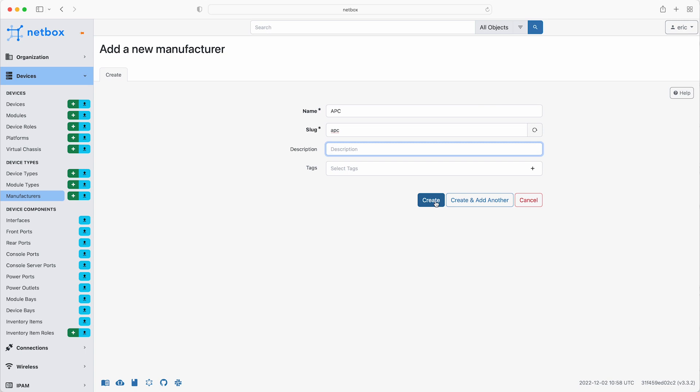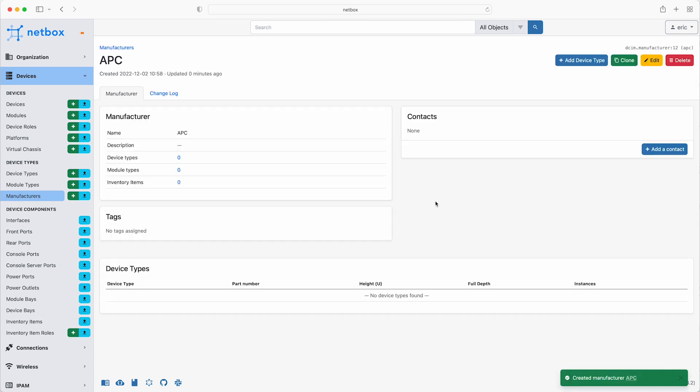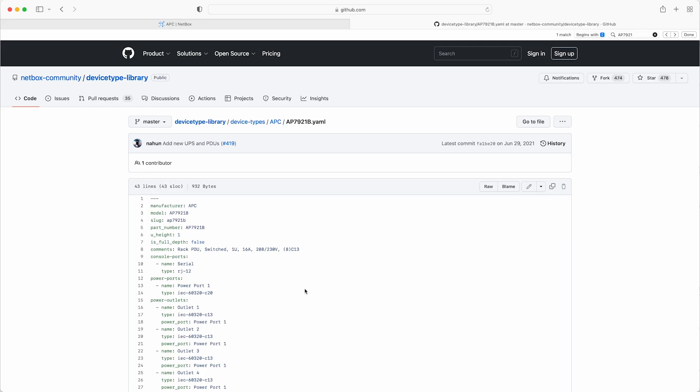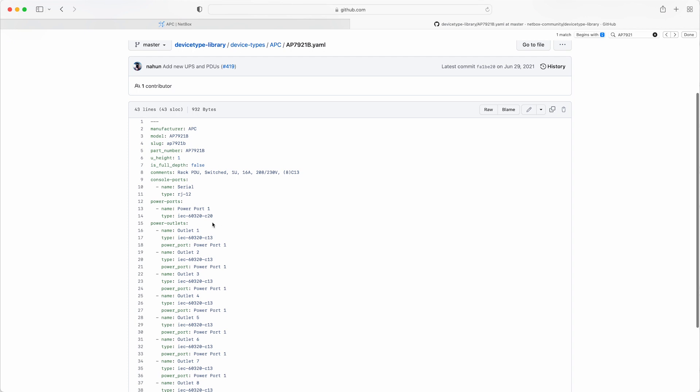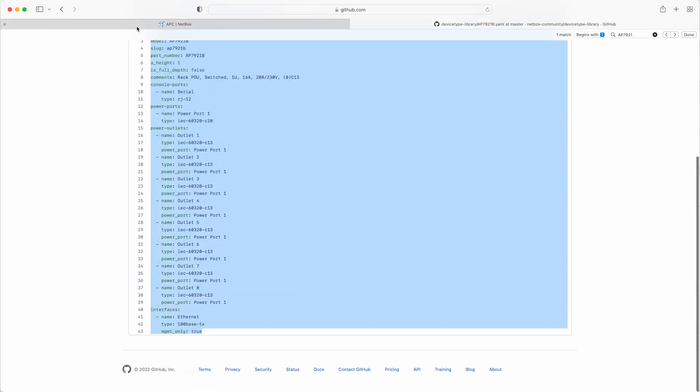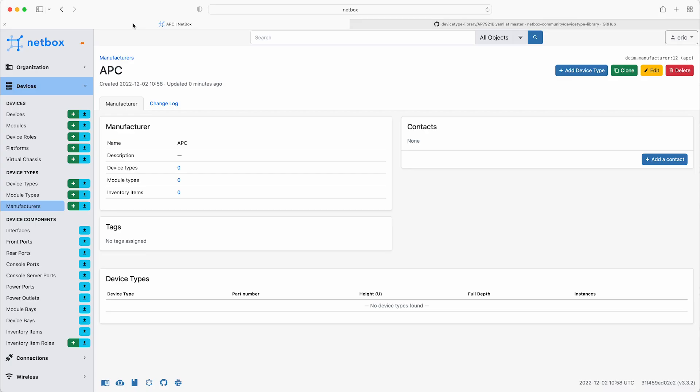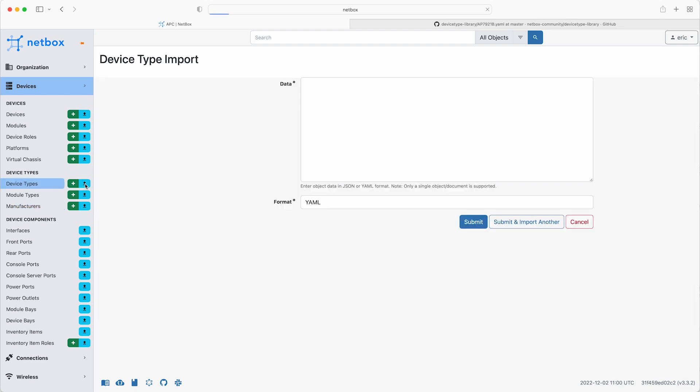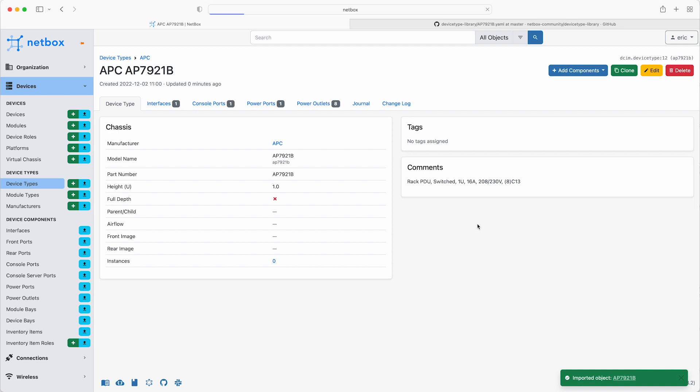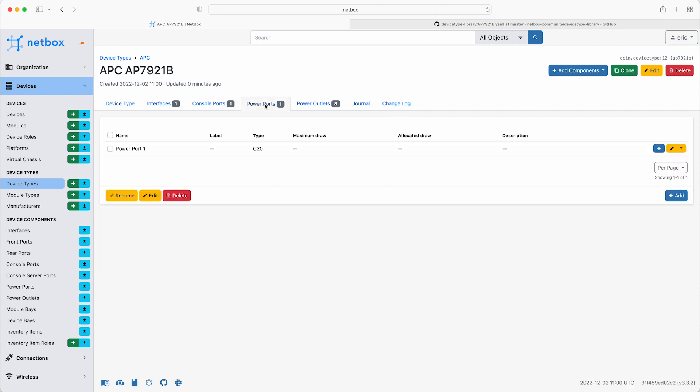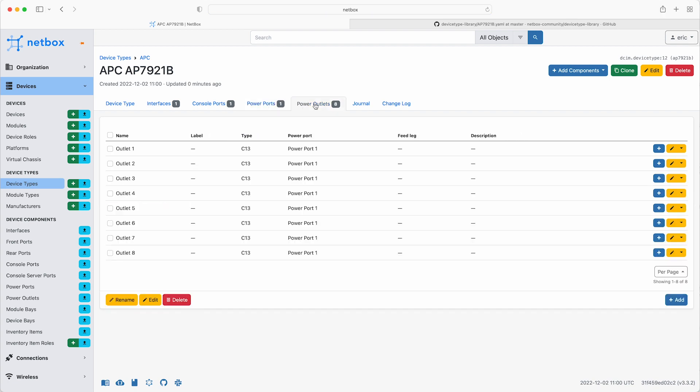Next, the device type that Eric has chosen is the AP7921B model. So you can add this by importing from the device type library. So from the GitHub repo, copy the YAML definition, and then in the UI, click on the blue import icon next to device types, and then paste in the YAML and click submit. So if you take a look at the device type, you can see that it has one power port that will connect to the power feed, and eight power outlets that the devices in the rack will connect to.